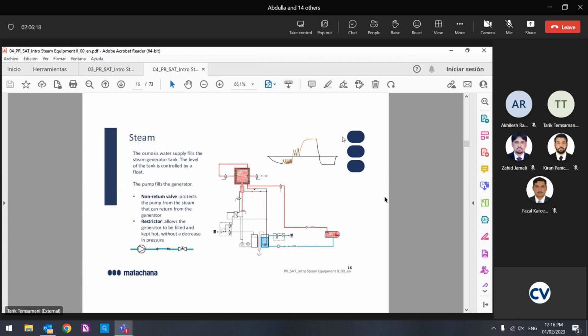Any questions, Satish? How many heating elements? Three heating elements are there. Are the three heating elements the same wattage or different? Same wattage. The difference is that in the SC1000, one heater works with one contactor and two heaters with another contactor, so there are only two contactors. One for one heater and one for two heaters. But the power is the same, all are the same. In the 5000 power charger, it is only one contactor. The 500 is also the same: one goes to one heater, and the second and third are connected to another relay.